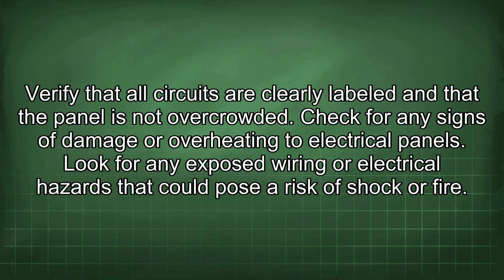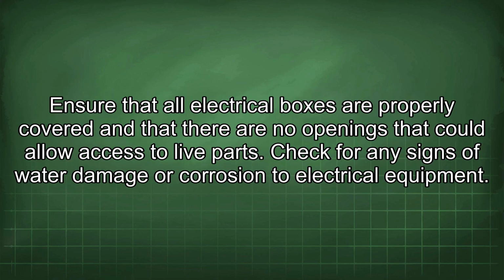Look for any exposed wiring or electrical hazards that could pose a risk of shock or fire. Ensure that all electrical boxes are properly covered and that there are no openings that could allow access to live parts. Check for any signs of water damage or corrosion to electrical equipment.